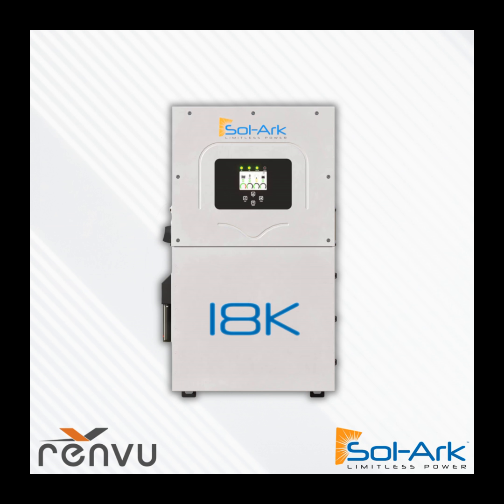On the conduit gutters — I don't know about Renvu, but I think they have that. I know Discover batteries sell a custom gutter; you can't tell by looking at it, but they've factored in airflow considerations. The battery manufacturer's gutter accessory lets you butt the gutter directly into the Sol-Ark as shown, because there's more to that airflow than meets the eye, since it's happening behind the unit.